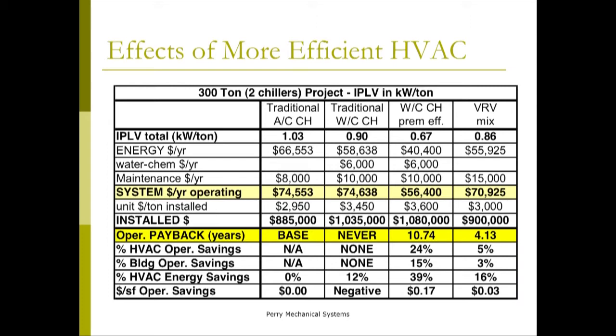So our traditional air-cooled system is the baseline. A traditional air-cooled system versus a traditional water-cooled system would really never pay back in a 300-ton range unless you're looking at the replacement cost of the air-cooled chiller being more frequent than the water-cooled one. These premium efficiency systems, like a magnetic chiller, can get about a 10-year payback, plus you get the benefit of that equipment lasting longer. So even though 10 years isn't always attractive to a building owner, considering the additional capital investment down the road, it can become a lot more attractive.